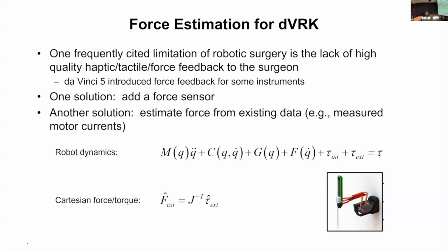So now the DV5, the latest generation of Da Vinci, has introduced force sensing for some instruments. On the one hand, I'm glad I published most of my papers on force estimation before that came out. But what they had to do here is they actually added strain gauges to their instruments, which you can imagine adds a little bit to the cost of the instrument, but it actually more than doubles the cost.